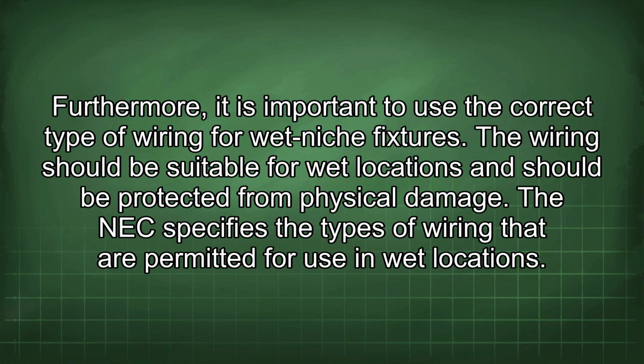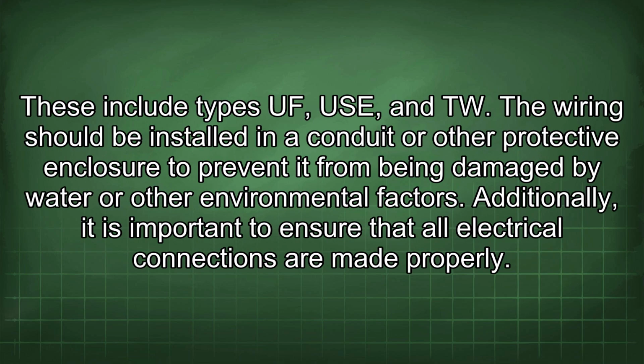Furthermore, it is important to use the correct type of wiring for wet niche fixtures. The wiring should be suitable for wet locations and should be protected from physical damage. The NEC specifies the types of wiring that are permitted for use in wet locations. These include types UF, USE, and TW.